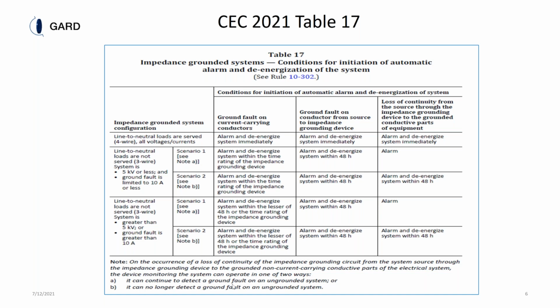One is if you are able to detect a ground fault in an open circuited, ungrounded system, which basically means if you have the loss of continuity from the XO bushing to the resistor, you basically have an ungrounded system. If you have a short in the XO bushing to ground, you have a solidly grounded system. So we are able to detect a ground fault in that scenario. So as you can see, there are different things you need to do depending on the fault. Whether you have an open circuit or short circuit, you need to alarm and de-energize within 48 hours.